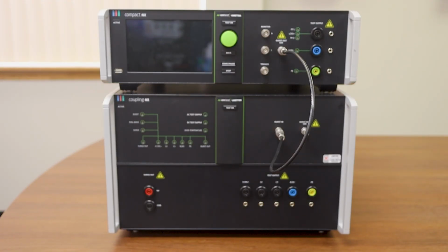Line synchronization is the degree on the AC sine wave where the surge pulse is placed. This requires communication from the transient generator to the CDN to allow for the placement of the pulse at the corresponding degree which the user selects. This isn't an issue for electrical fast transients or for surge testing DC lines. We have also seen that attempting to make adjustments to allow for different manufacturers to operate together for line synchronization can cause damage to the transient generator or the other manufacturer's coupling-decoupling network.